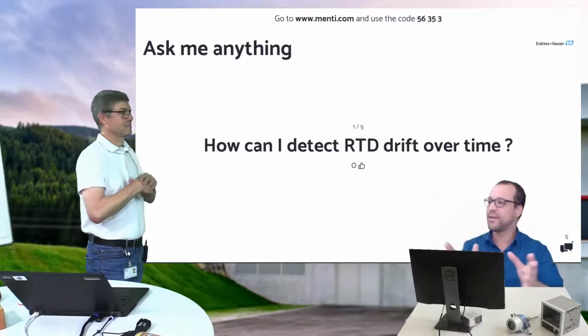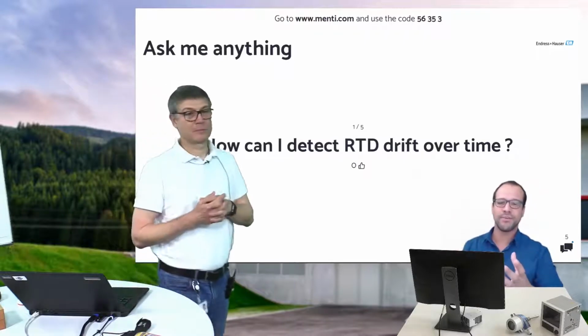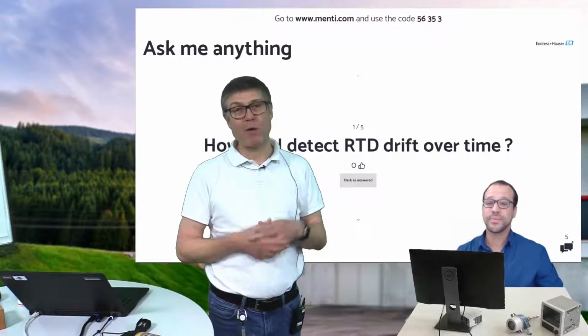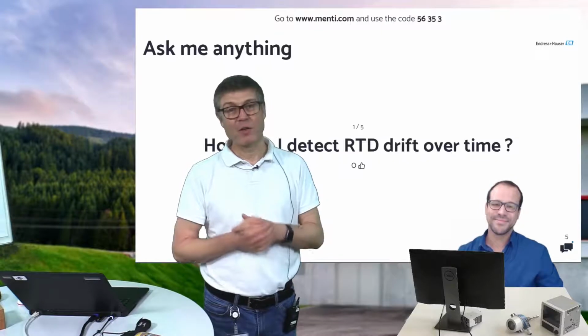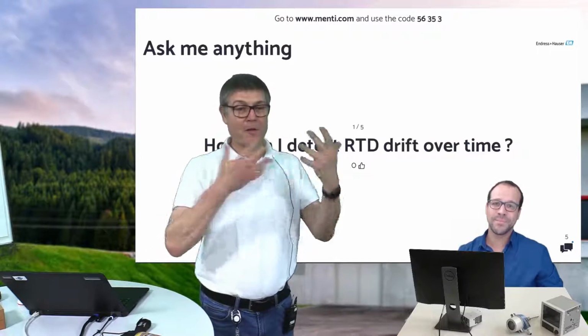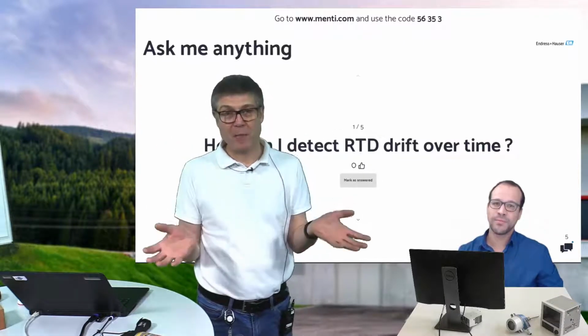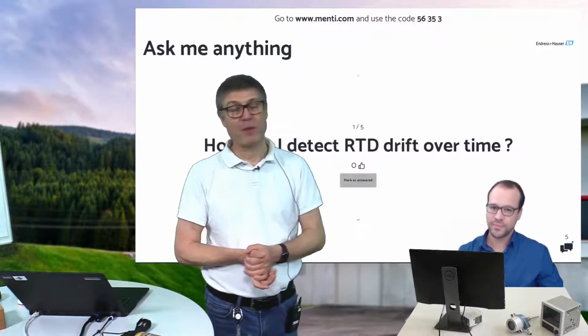Great. And now we have a couple of questions. If you have more, please just shout at us. RTD drift over time. Basic, simple answer: calibration. Calibration by dismounting it and putting it into a calibration, or by using a self-calibrating sensor for special applications. But there's no other way to detect the drift than to compare the result of the RTD with a reference. And the reference is a calibration environment or a physical fixed point. So there's no other answer than calibration.